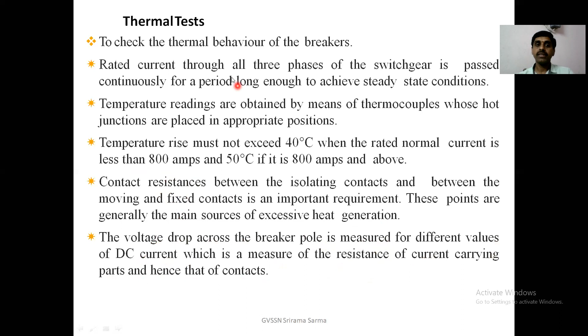What is the indication of this? The voltage drop across the breaker pole is measured for different values of DC current, which is a measure of the resistance of current carrying parts and hence that of the contacts. And by measuring the resistance of the current carrying contacts, the thermal test can be performed.